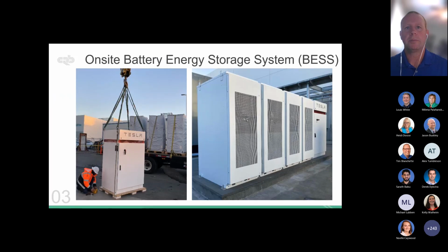We ended up going with a 1 megawatt-hour battery energy storage system, so 1 megawatt of solar and 1 megawatt-hour of battery. This is the Tesla Megapack, a pretty small footprint, 6 feet deep, 20 feet wide. We used to have Conex containers that were about twice the size and half the capacity, maybe just 5-10 years ago. So the density of these energy storage systems has accelerated quickly.